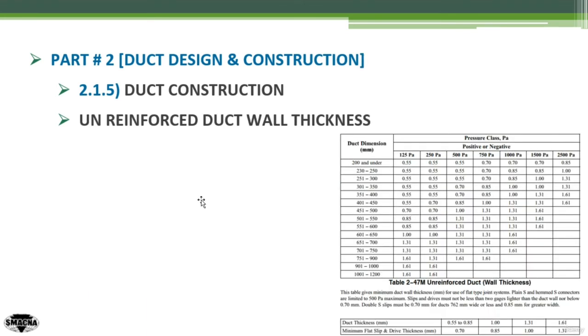Going back to the previous table, the duct sheet metal thickness of 0.7 mm in the second case lies between 0.5 and 0.85, meaning you can use a minimum flat drive slip and drive thickness of 0.7 mm. This gives you a hint that you only need to know the duct operating pressure class, and the duct sheet metal thickness will be calculated accordingly. From this, you can specify any details related to the joints, slip connections, or whether any reinforcement is required for the duct.